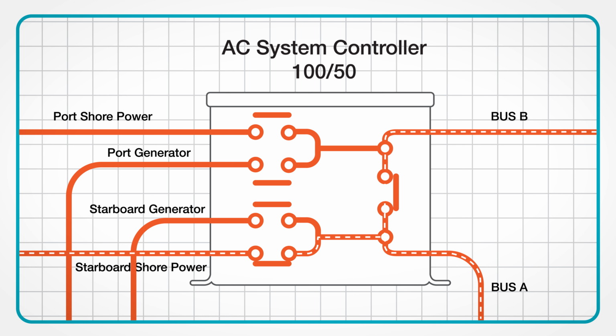We need more power, so we go out and connect the port shore power cable in the marina supply. We've now got voltage coming into the second input. To take advantage of that, we disconnect Bus B from the starboard shore power and connect the port shore power to Bus B. Now we've got 2 shore cords in use, each supplying its dedicated bus.